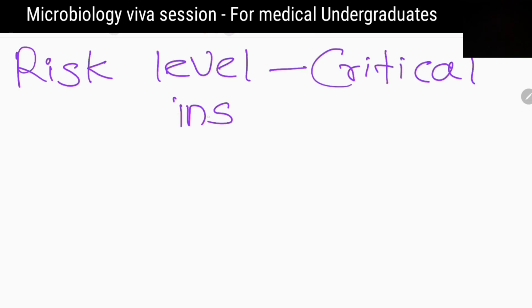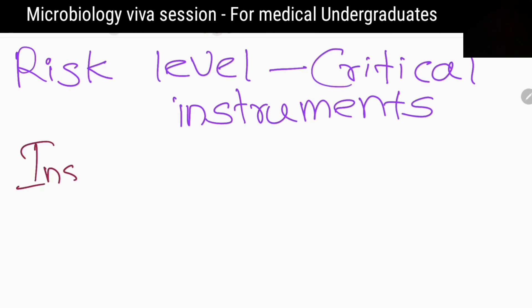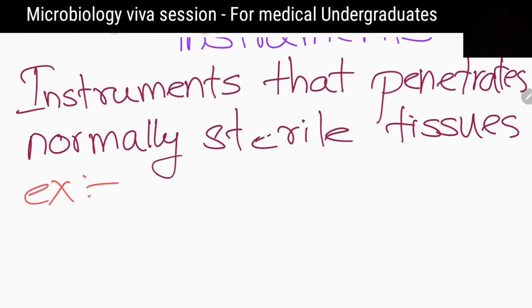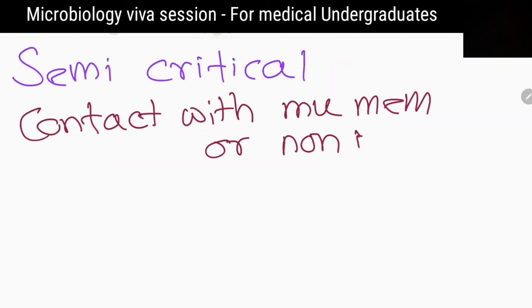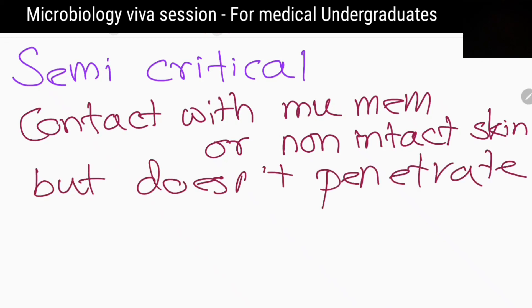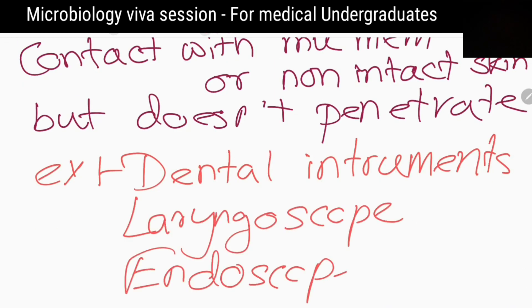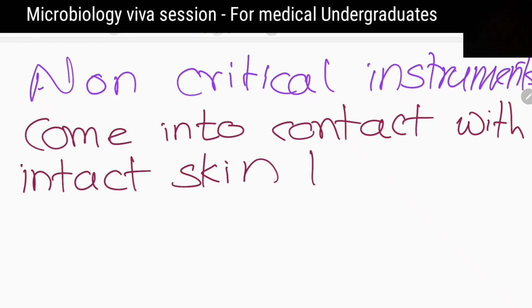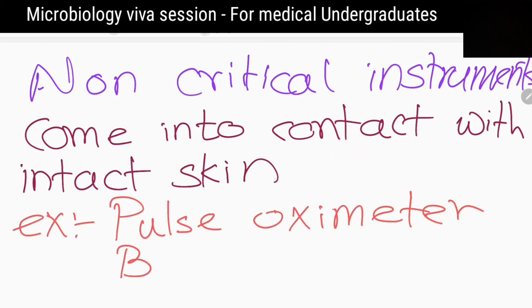When considering the risk, what are critical instruments? Instruments that penetrate normal sterile tissues and spaces. Give me an example. Surgical instruments. Classify other instruments according to risk. Instruments that contact mucous membranes or non-intact skin are called semi-critical instruments — for example, dental instruments, laryngoscopes, and endoscopes. Instruments that come into contact with intact skin, like pulse oximeters, blood pressure cuffs, and thermometers, are called non-critical instruments.